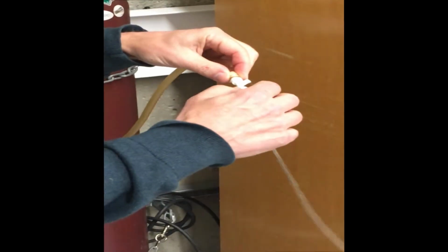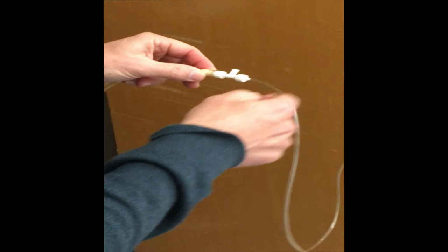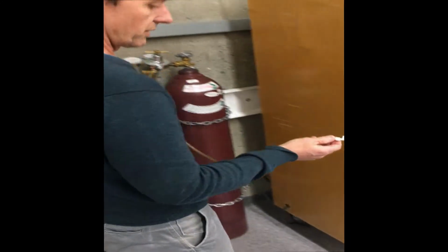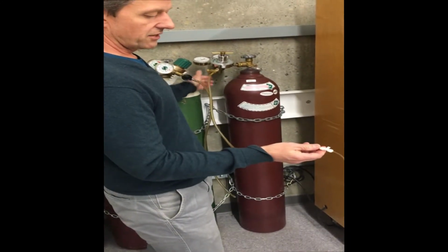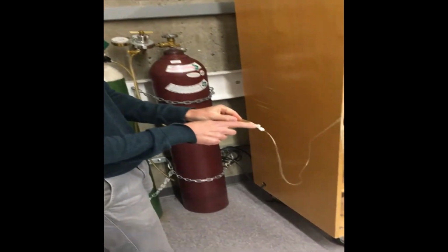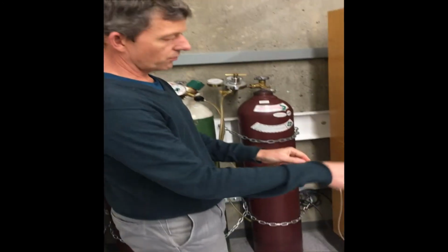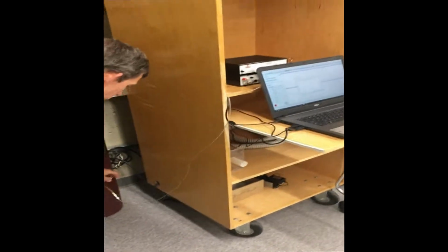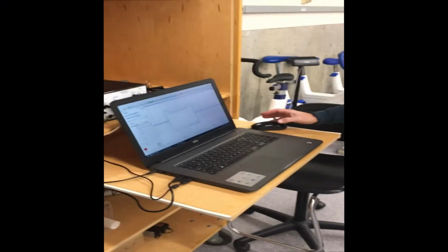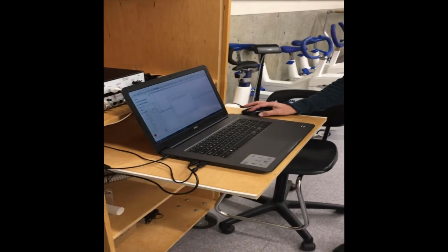Now all we need to do is take the end of our sample line, and the connection here, it's a 3-way or a T connection. It just simply locks in place. There's also a port here that allows any excess pressure to escape because we do not want to overpressurize the gas analyzer. So all we do now is open this up, and you can hear that there's air flowing through there. So we know now that the air is going into the gas analyzer and it's able to sample the sample gas. So it's saying, have you hooked up to the calibration gas? Is it flowing? We say yes.